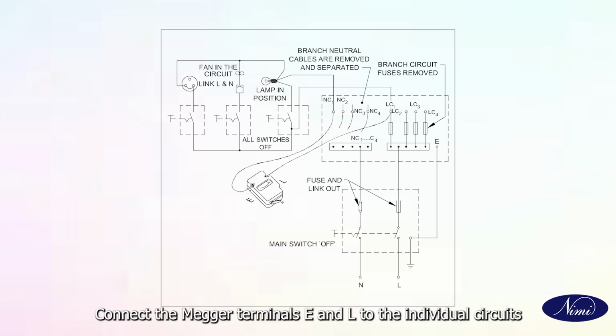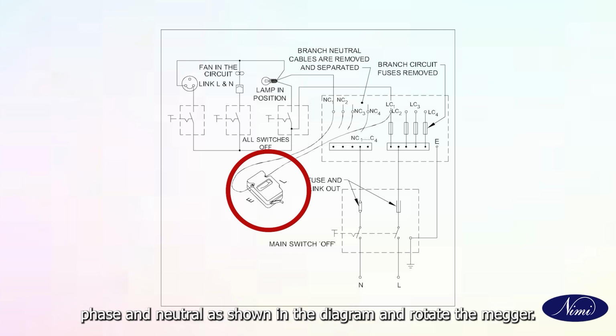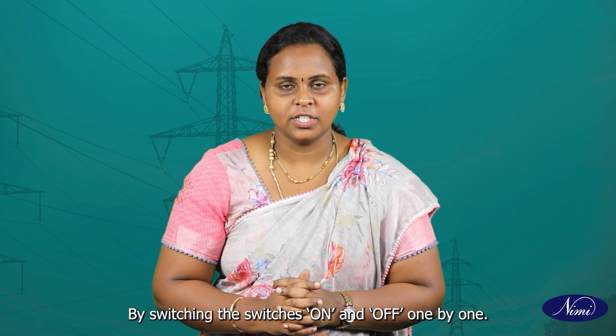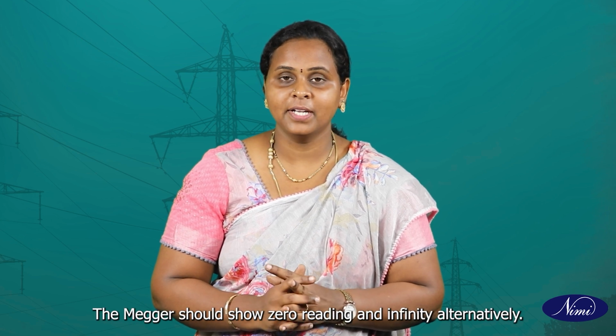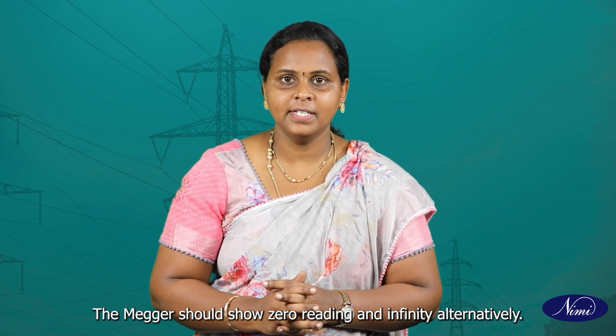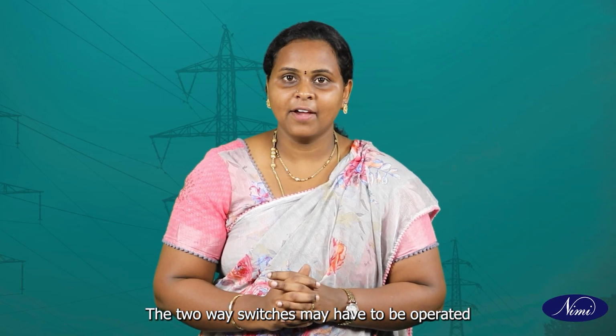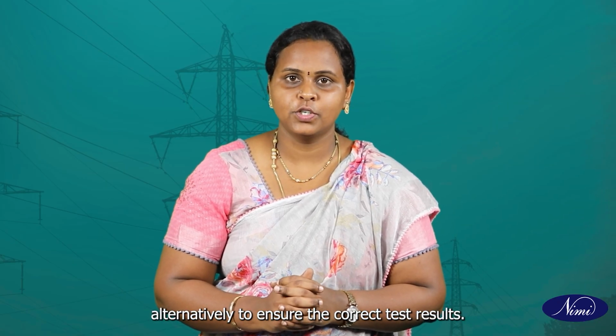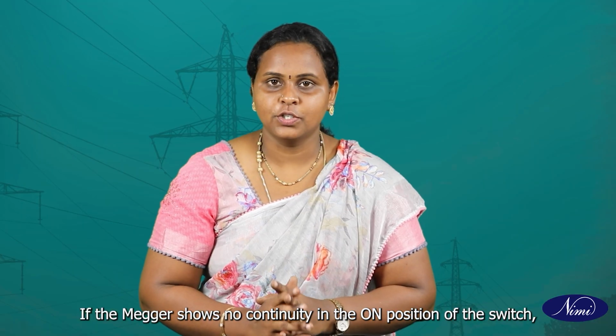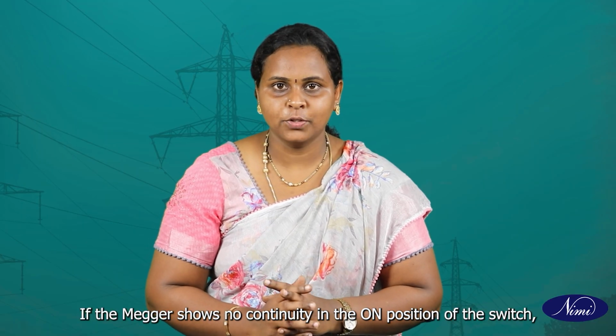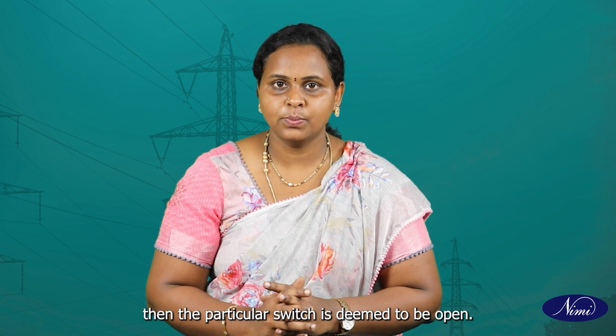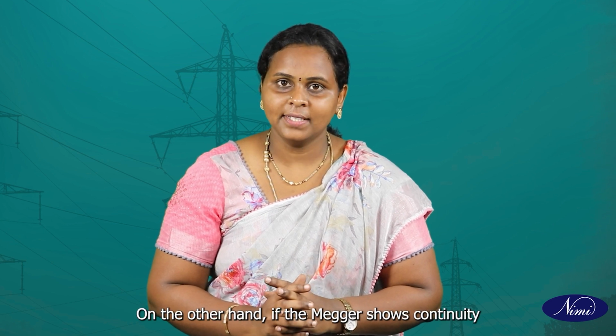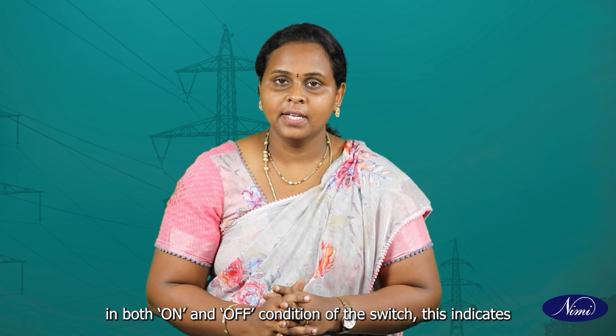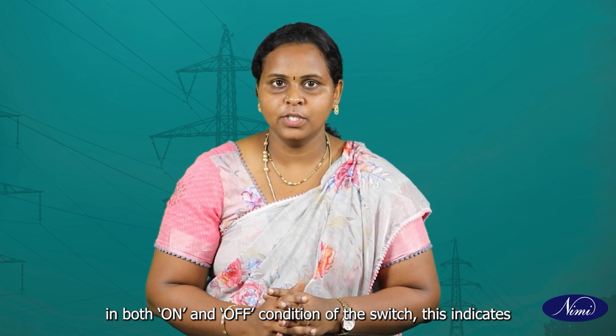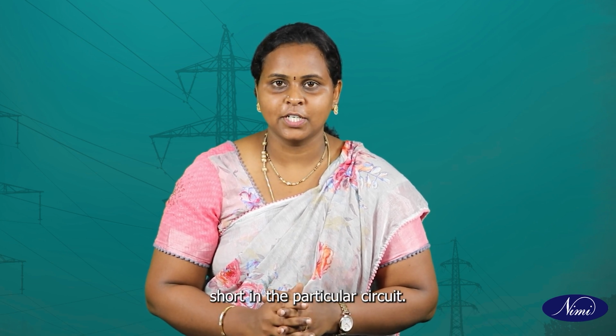Connect the megger terminals E and L to the individual circuit's phase and neutral as shown in the diagram and rotate the megger. By switching the switches on and off one by one, the megger should show 0 reading and infinity alternately. The two-way switches may have to be operated alternately to ensure correct test results. If the megger shows no continuity in the on position of the switch, then the particular switch is deemed to be open. On the other hand, if the megger shows continuity in both on and off conditions of the switch, this indicates a short in the particular circuit.